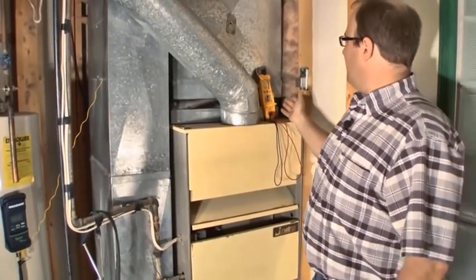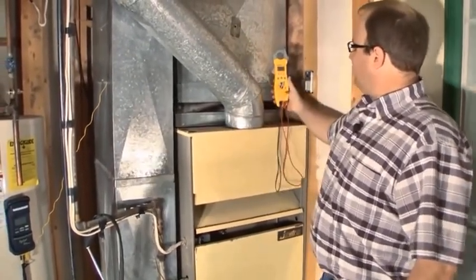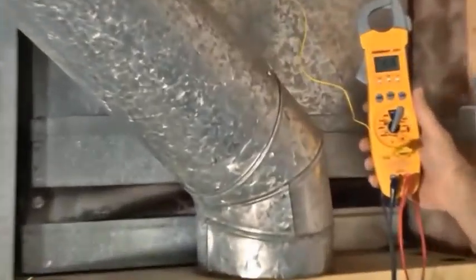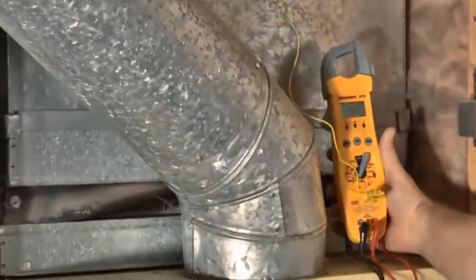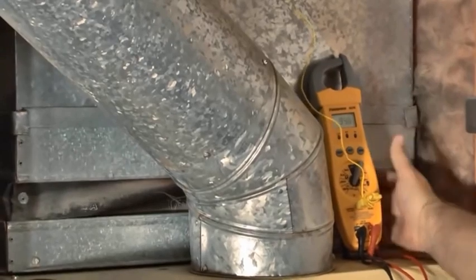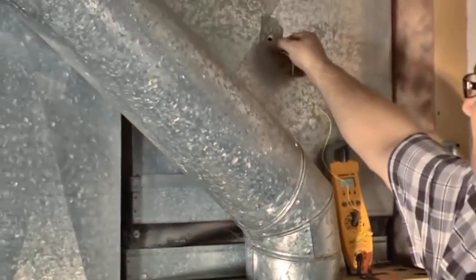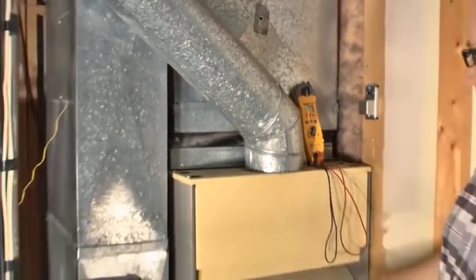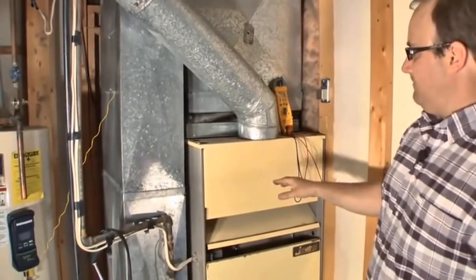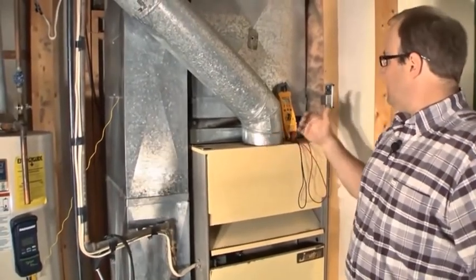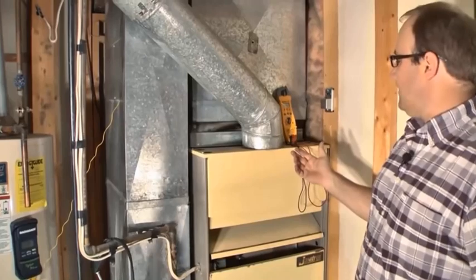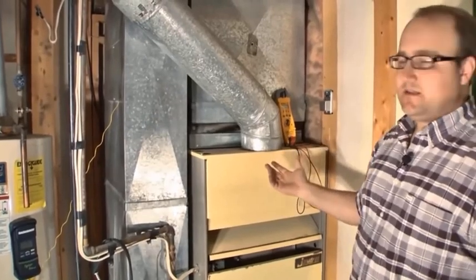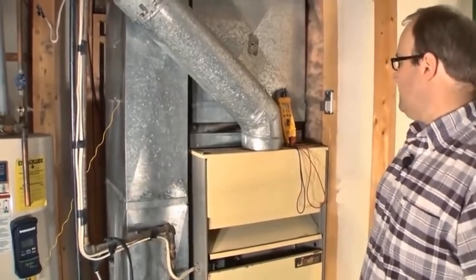Those are the three temperatures we look for. Okay, we got our furnace running. You can actually see the temperature starting to climb here, but the fan has not kicked on yet. We're waiting for a fan kick on temp. So the heat exchanger will heat up, gets to a certain temperature, then it turns the fan on. We don't want to turn the fan on instantly, otherwise we blow cold air.